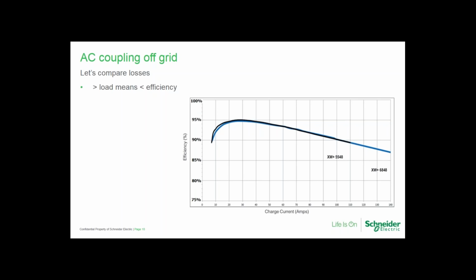So what that means is if we're AC coupling and we're storing that energy rather than consuming it in real time with the load, the magnitude that we're charging the battery with that AC coupled power is going to be directly related to the efficiency. Likewise, the inverter efficiency is fairly similar to the graph you see here. So you're getting losses when storing the energy, and also when discharging. It's important to realize that when you're designing an AC coupled system off grid, you want to make sure that your loads are occurring during solar hours.